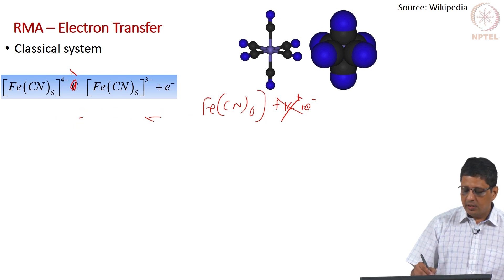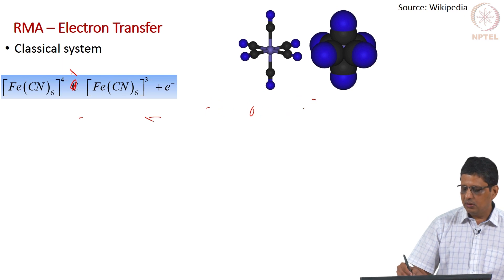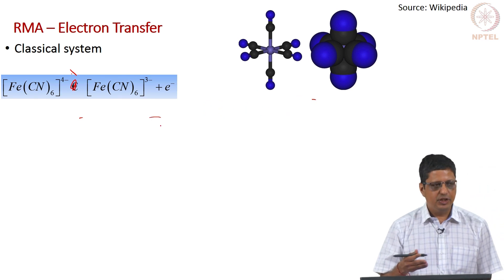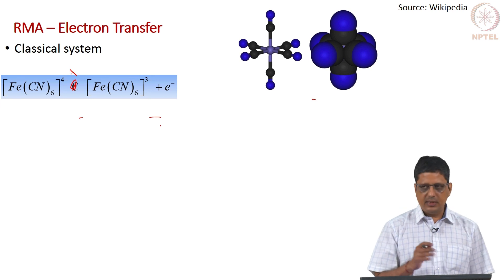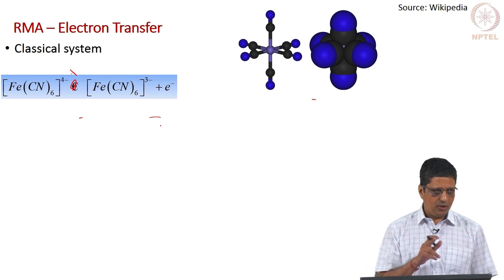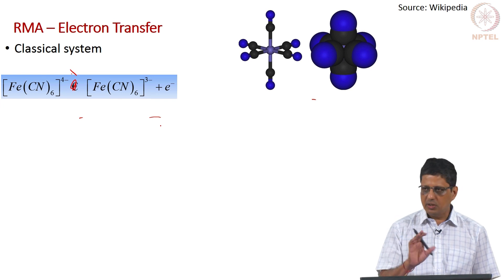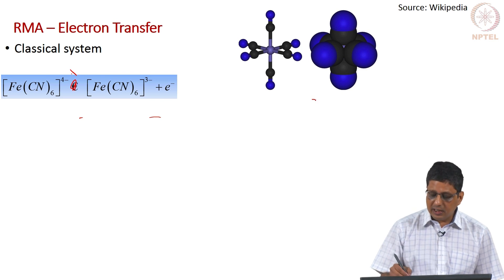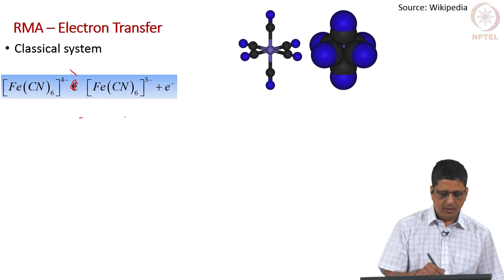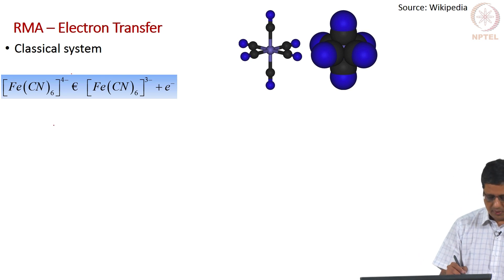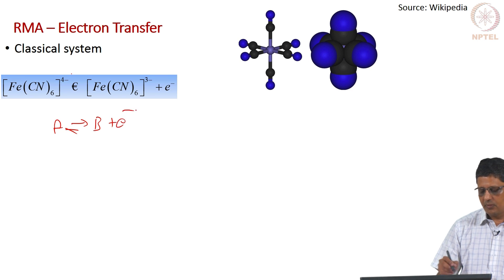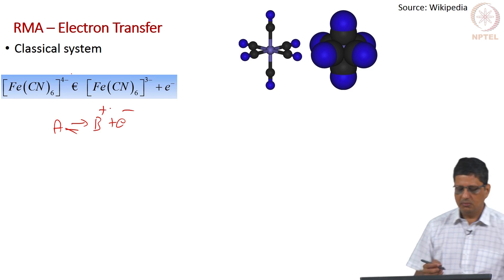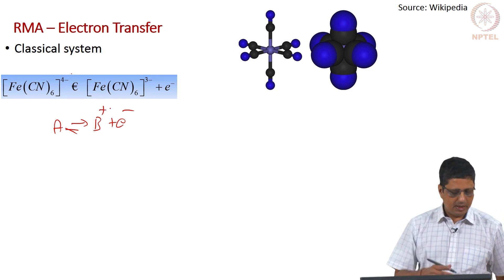So this is normally taken as a classical system. In our lab, if we suspect something is wrong, we take a gold electrode — ideally we should use a platinum electrode — put this, measure the spectrum. If it comes correctly, we are okay; if it does not come correctly, maybe the reference electrode is not good or the instrument has some problem, and we have to sort it out. This is something where we expect it to behave nicely. We will call this as A going to B plus an electron, a reversible reaction.